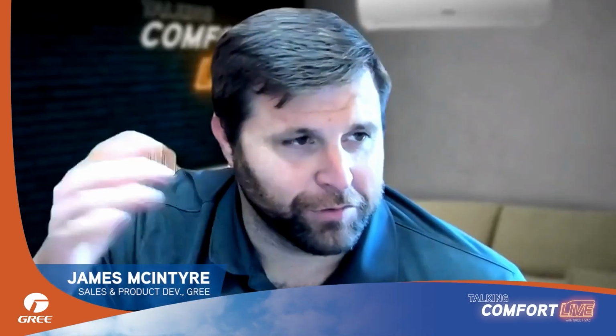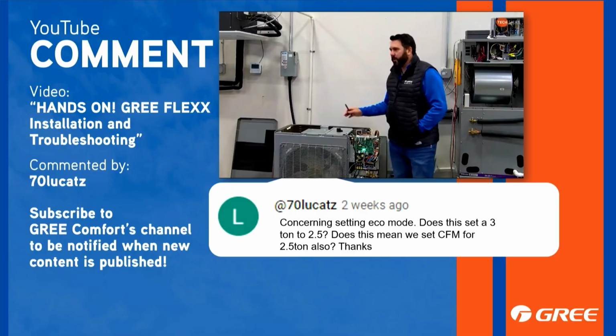Right. I mean, we aren't relying on a low pressure switch, for example. Now, there are many units out there that don't have a low pressure switch at all. And the unit will absolutely run with nothing in it until that overload trips and keeps tripping and keeps tripping. And that's actually another thing that I don't think we talk about enough: our overloads are external. So you trip an overload enough, eventually they want to give up. Well, sure, you're replacing the overload on top of the compressor, but you don't have a bad compressor now because of it. You're switching an overload.